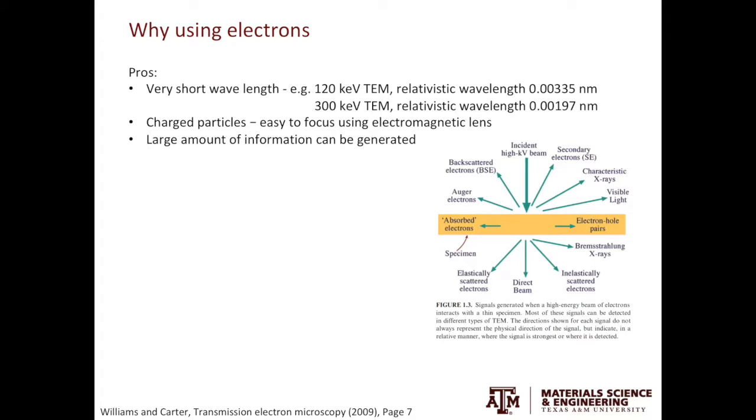There are many advantages of using electrons to form images. First of all, electrons have very short wavelengths. In a 120 kV TEM, the relativistic wavelength of the electron beam is 0.00335 nanometers. At a higher acceleration voltage, at 300 kV, the relativistic wavelength is further reduced to 0.00197 nanometers. Just to give you a reference, the typical wavelength for visible light is around 400 nanometers. So the wavelength of the electron beam is orders of magnitude smaller than the wavelength of visible light.